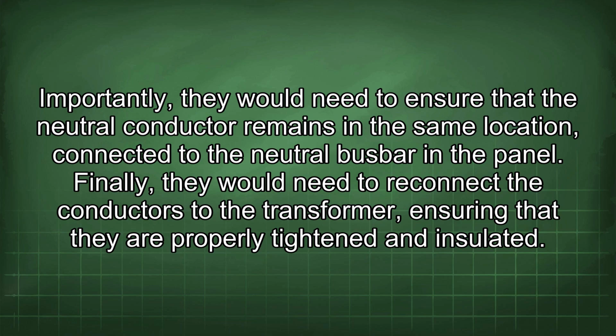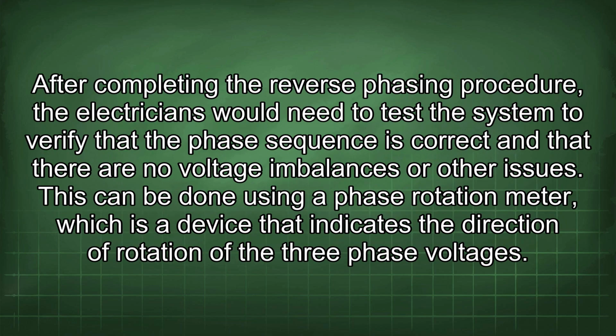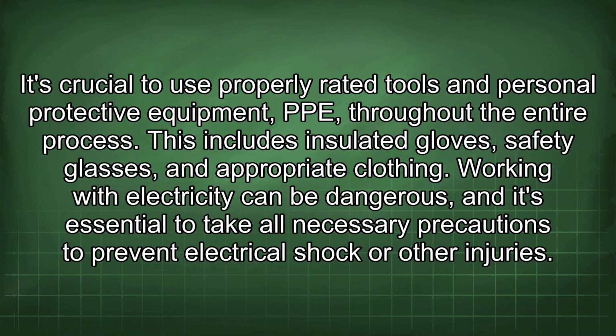After completing the reverse phasing procedure, the electricians would need to test the system to verify that the phase sequence is correct and that there are no voltage imbalances or other issues. This can be done using a phase rotation meter, which is a device that indicates the direction of rotation of the three-phase voltages. It's crucial to use properly rated tools and personal protective equipment, PPE, throughout the entire process. This includes insulated gloves, safety glasses, and appropriate clothing.